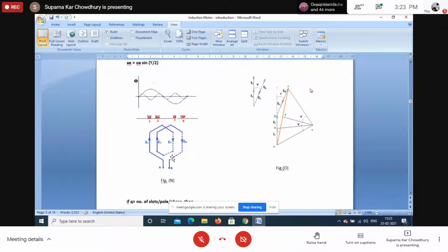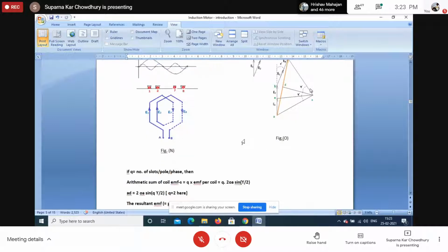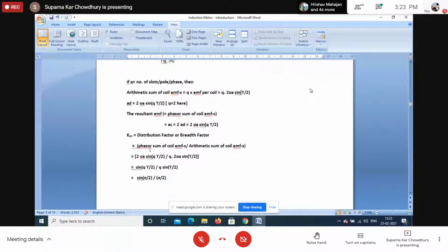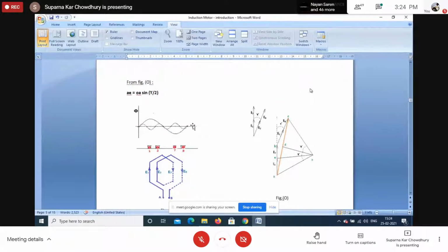So the summation of these 4 EMFs, that is between A and B, will be a phasor sum, no longer an arithmetic sum. We defined the distribution factor as the phasor sum of the coil EMFs divided by the arithmetic sum of the coil EMFs, and it was found to be sine q gamma by 2 divided by q sine gamma by 2, where q is the number of slots per pole per phase and gamma is the angle. This can be approximately written as sine sigma by 2 divided by sigma by 2, where sigma is the phase spread. Now this is Kd1, the distribution factor for the fundamental, because I have considered the fundamental wave here.